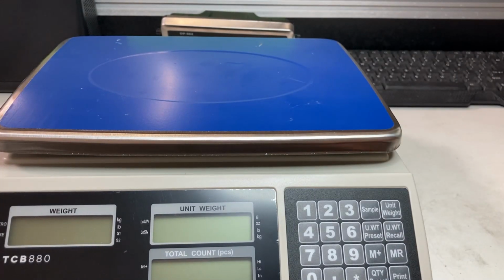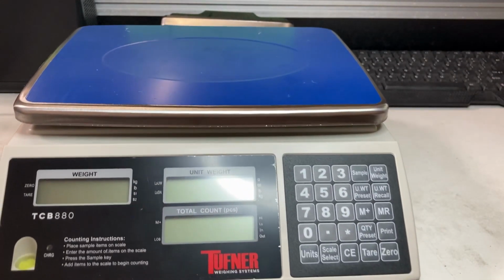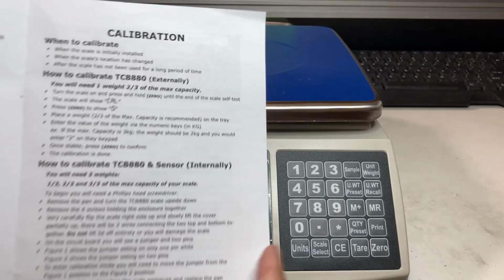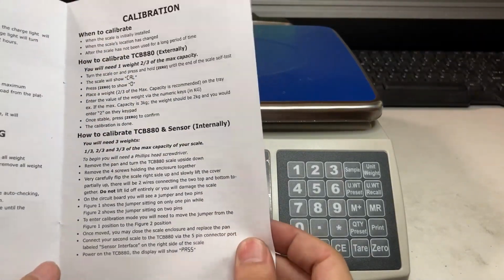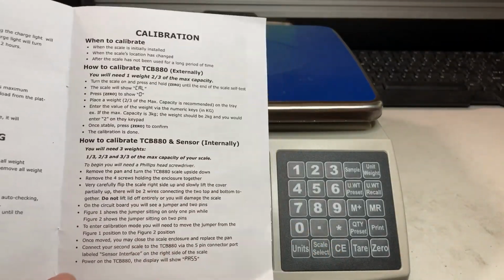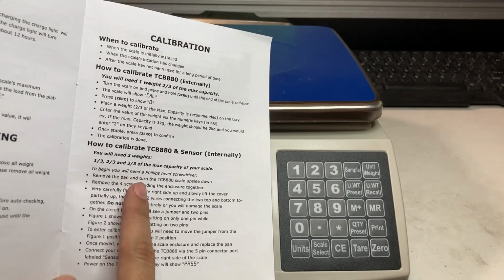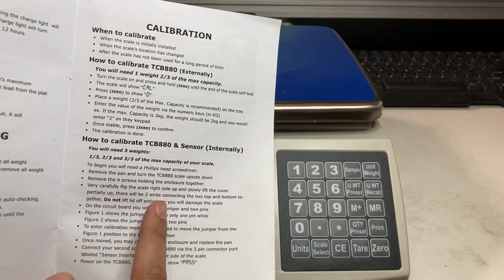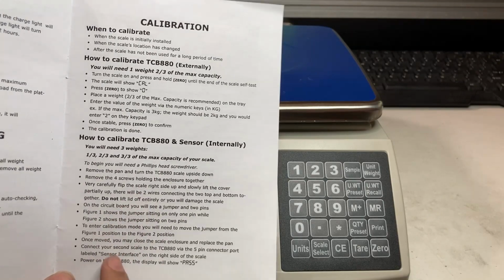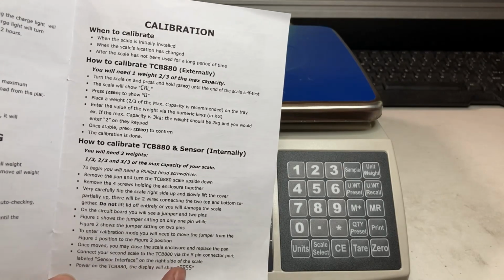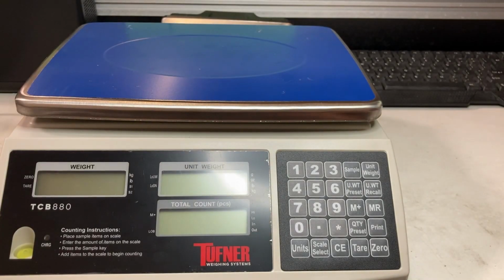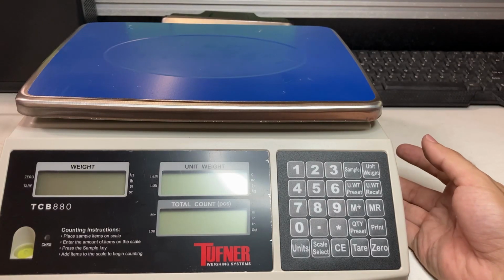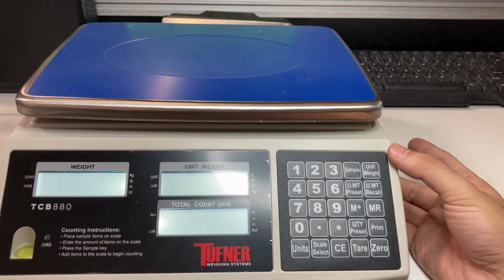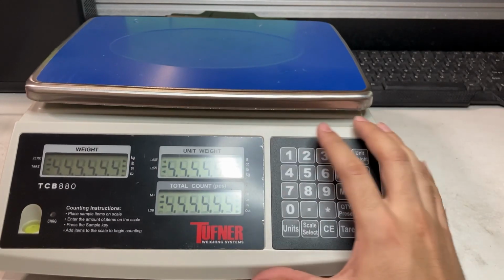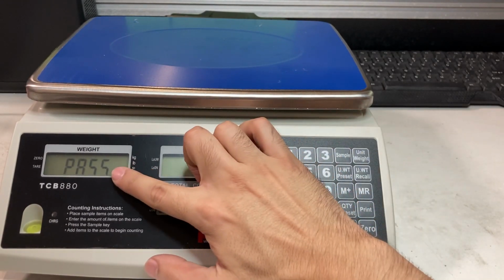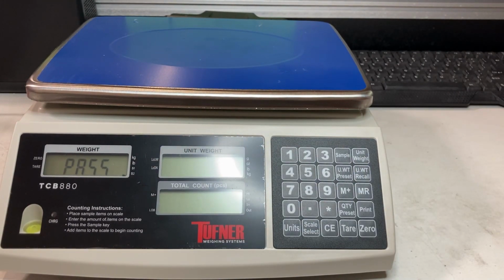Now you'll see in the instructions, in the calibration book, but it doesn't explain too well how to calibrate internally. It mentions remove the 4 screws, put the jumper pin, and you'll see a pass. So what you do is make sure the 2 pins are shorted, turn it on, and you'll see 'pass' here. That's what you're meant to see.